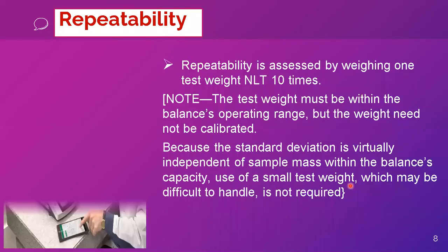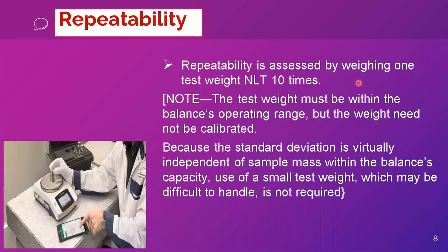What is repeatability? Repeatability is assessed by weighing one test weight not less than 10 times. The test weight must be within the balance operating range, but the weight does not need to be calibrated. For the repeatability test, I need to take a weight and observe it at least 10 times.